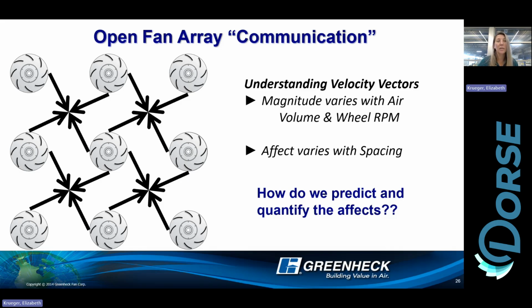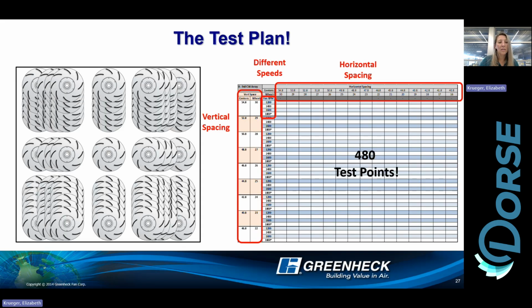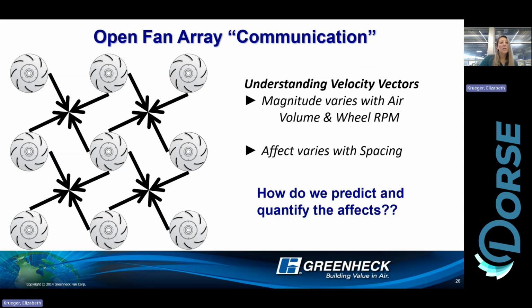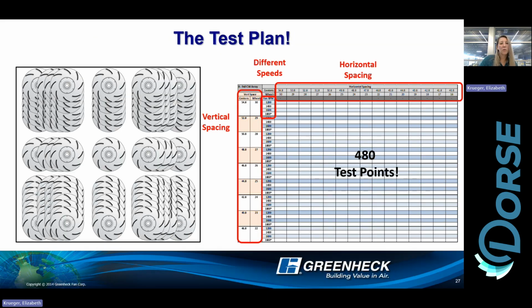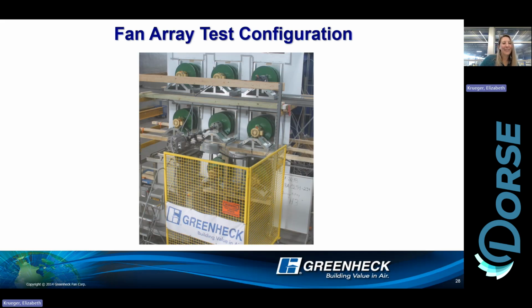So that we weren't guessing anymore. And since AMCA didn't do the testing, we actually did the testing. So with this, we set up some horizontal spacing and vertical spacing to see what the effects were. So when I'm talking about translation, here, I'll go back to that other picture. Basically, we wanted to see what would happen if we made these wheels closer together or farther apart. That testing and performance resulted in us testing about 450 or 480 different configurations. So pretty intense. This is kind of a look at what that configuration looked like in our shop, again, in the Innovation Center behind me there.